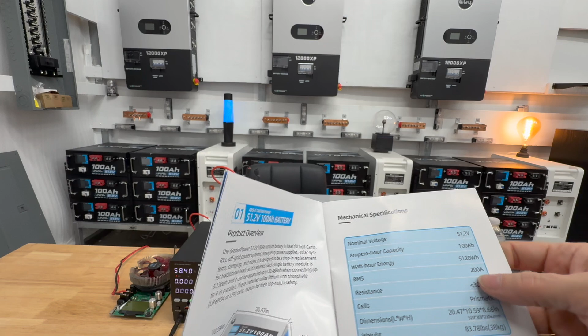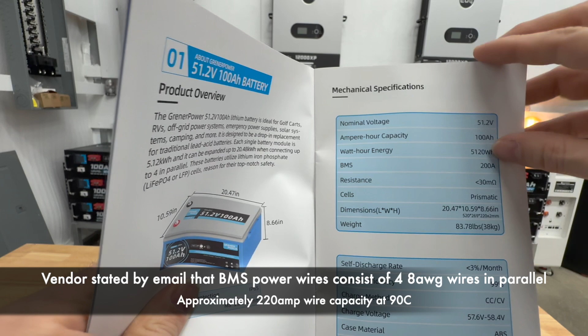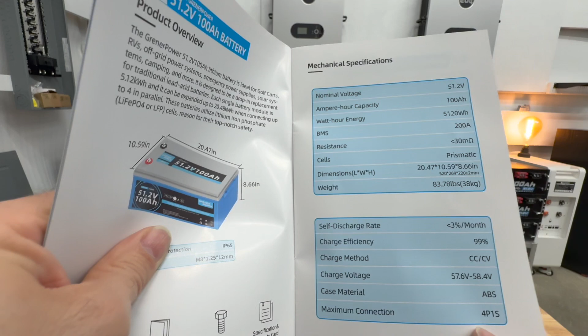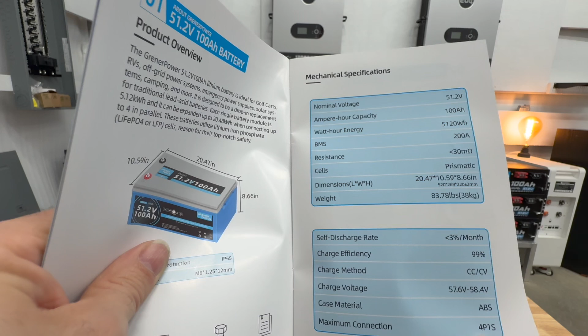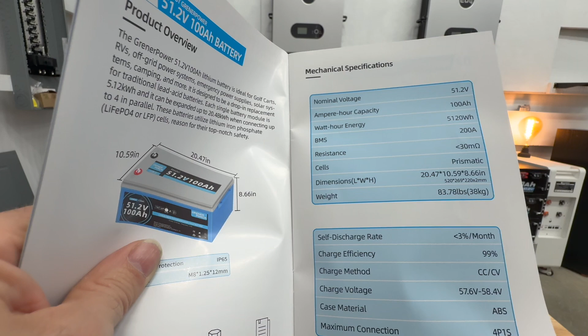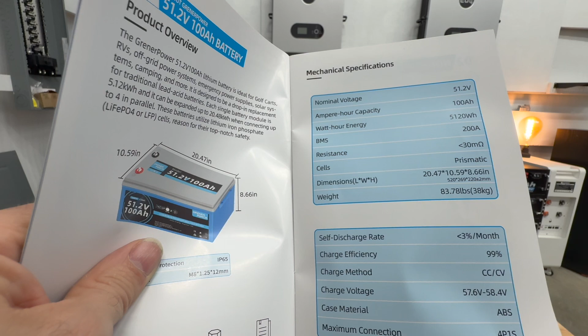So this battery has a wide variety of uses. I mean, you can use it for solar, but you can use it for other things as well. Once again, the BMS, you can see right here, 200 amp BMS on it. So that is kind of cool. It can really put out some serious power. As far as connections, 4P1S, so 4 in parallel, 1 in series. So recommended not to put more than 4 in parallel, I'm guessing, because if you put more than that, you're going to want to have dedicated fuses so you don't run into any sort of issues.